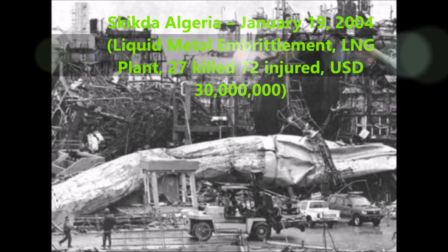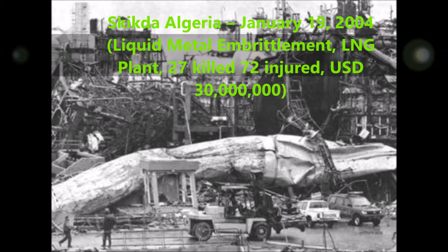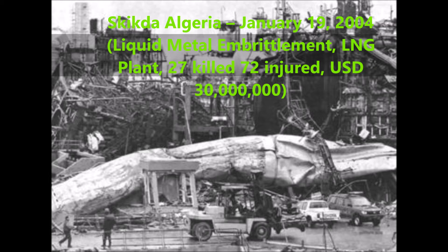The most probable source of ignition was the boiler at the north end of Unit 40. The report concluded that the escaped gas was from the cryogenic heat exchanger. After investigation, the reason was found to be liquid metal embrittlement.